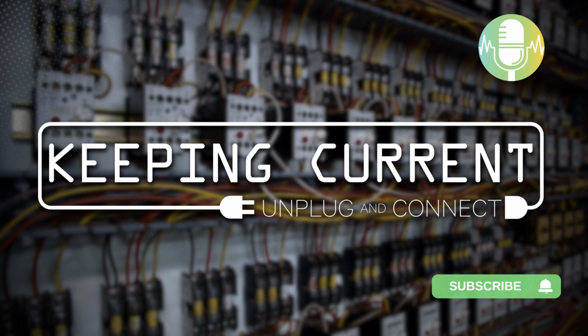And really the foundation, in my opinion, are these two together. Because if you only do one, then there's no guarantee the other one works. And so if you do breaker settings, but you don't do the maintenance that goes along with it, who knows if that breaker is actually going to trip? And again, if you do the maintenance on it and you know that breaker is going to trip, but you don't have it set accurately, then you don't know if you're truly protected from an arc flash event and when that breaker is actually going to trip because it's not set correctly.